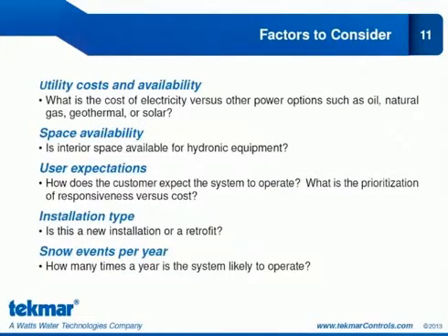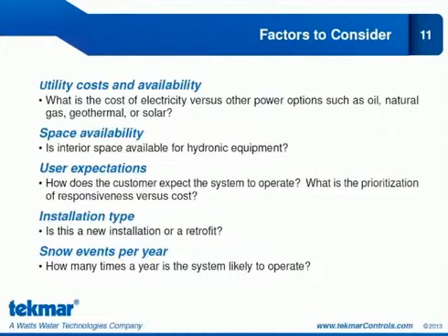The factors you should consider when choosing between electric and hydronic include utility cost and the availability of other power options — compare the cost of electricity to oil, natural gas, geothermal, or solar. You also need to consider your space availability for hydronic equipment. Look at user expectations: how does the customer expect the system to operate, and how do they feel about responsiveness versus cost? Also consider whether it's a new installation or a retrofit, since electric cables are easier to retrofit. And finally, how many snow events per year does your area see? The more times per year your system operates, the more you'll want to look at cheaper fuel options.